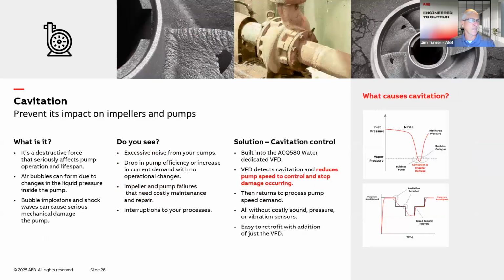Let's focus on the second issue that's damaging pumps and impellers, and that's cavitation. Cavitation is caused by the inlet side or upstream side of the pump being starved for water. There may be an obstruction in the flow or a partially closed valve that creates low pressure on the pump inlet. The result is cavitation. That's a destructive force that damages the pump impeller due to erosion. You can actually audibly hear the sound of the pump change when cavitation is happening.